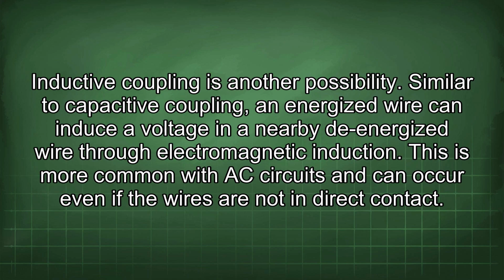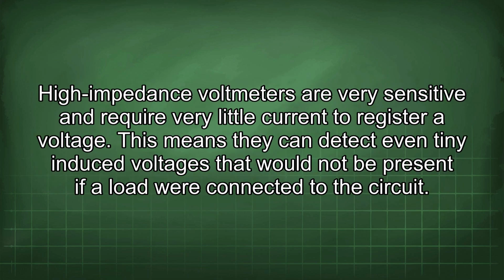Inductive coupling is another possibility. Similar to capacitive coupling, an energized wire can induce a voltage in a nearby de-energized wire through electromagnetic induction. This is more common with AC circuits and can occur even if the wires are not in direct contact. High impedance voltmeters are very sensitive and require very little current to register voltage. This means they can detect even tiny induced voltages that would not be present if a load were connected to the circuit.